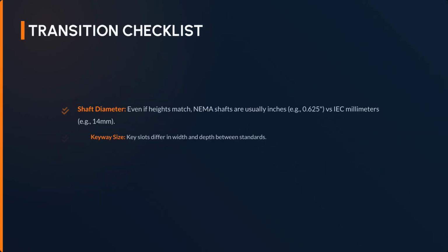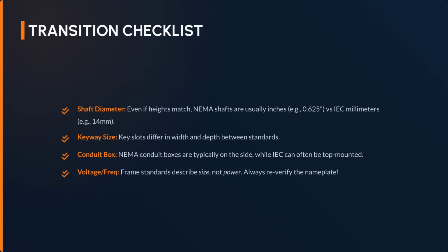When transitioning, be sure to check the shaft diameter, keyway size, and conduit box location. Remember, frame standards describe size, not power, so always re-verify the nameplate for voltage and frequency.